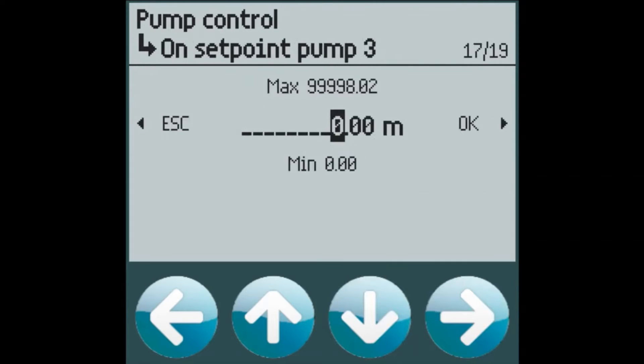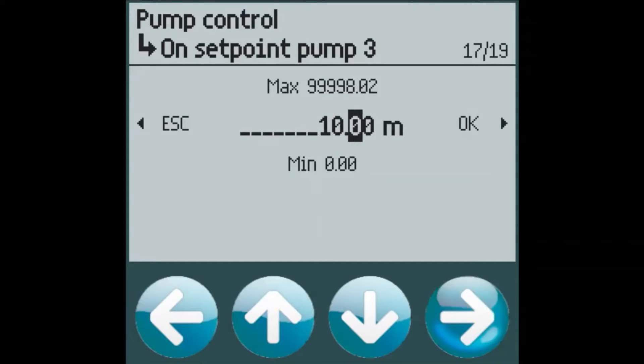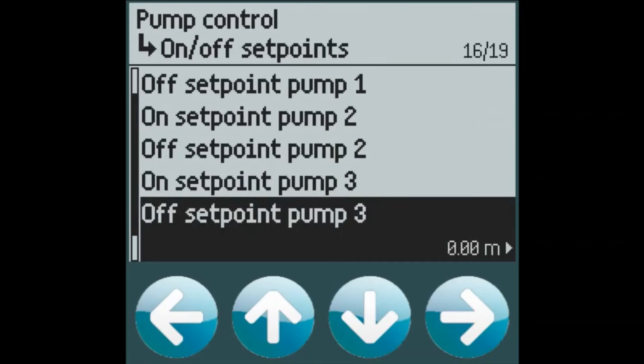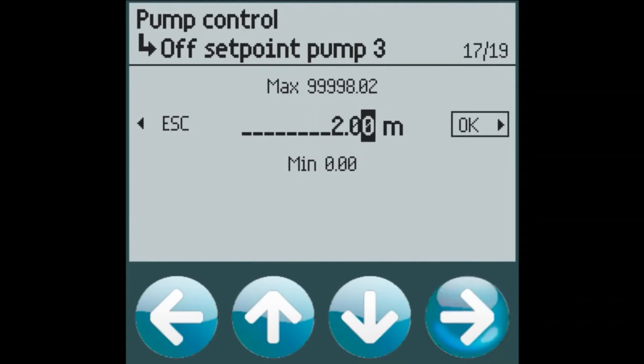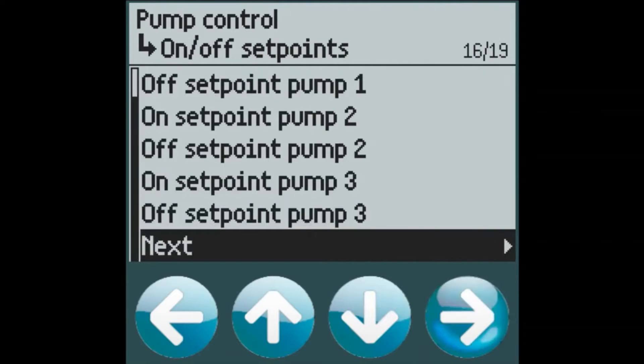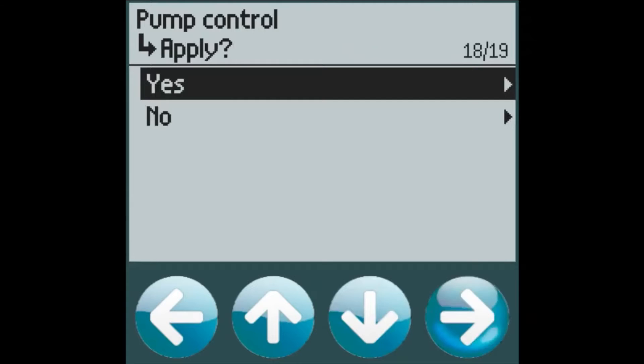And pump 3 will turn on at 10 meters of level. So all of our pumps will turn off at the 2 meter level mark. And there we go. We've configured our pump control for on/off setpoints.